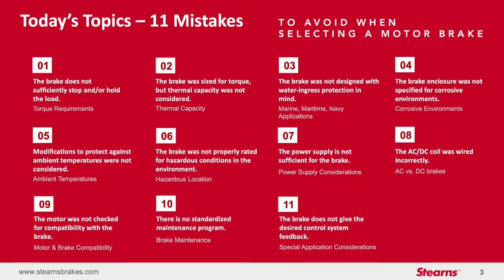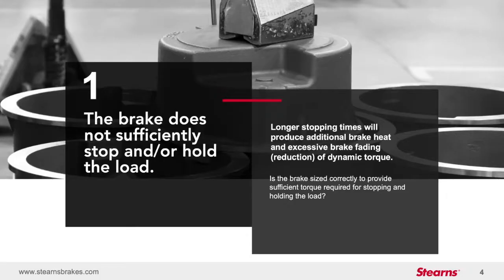Please leave those questions in the Q&A box, and we'll go through as many as we can at the end of the session. Starting off with the first common issue to avoid, the brake does not sufficiently stop and or hold the load. This is a common issue we hear customers run into and is often due to simply not calculating your brake torque requirement correctly. Brakes should be sized for the required loads and not significantly oversized. Oversizing a brake can cause problems, as does undersizing.